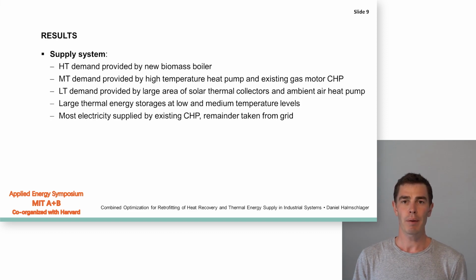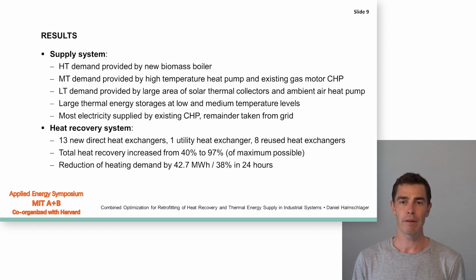So let's quickly sum up the results of the case study. I've already talked quite a bit about the new supply system and the new heat exchangers. But when looking at the levels of heat recovery, we see that the new system increases the heat recovery from 40% to 97% of maximum available heat recovery. This reduces the overall heating demand by over 40 megawatt hours or 38% within the covered 24-hour period.